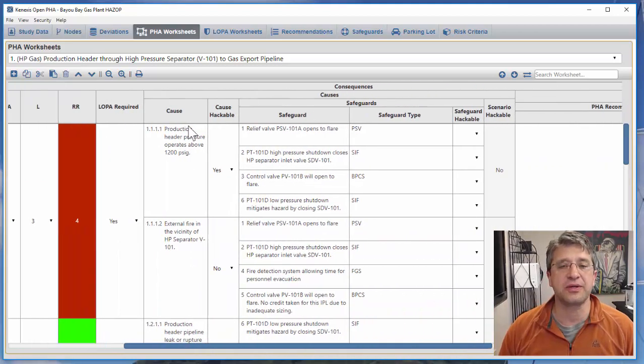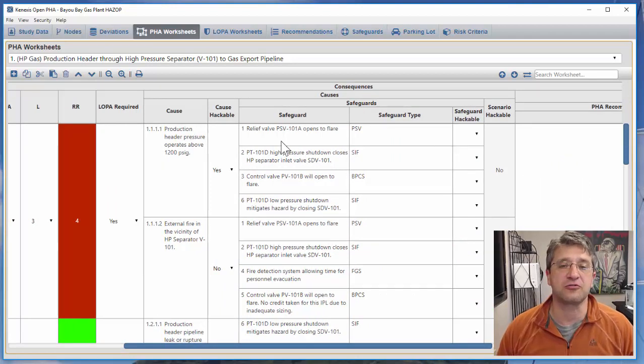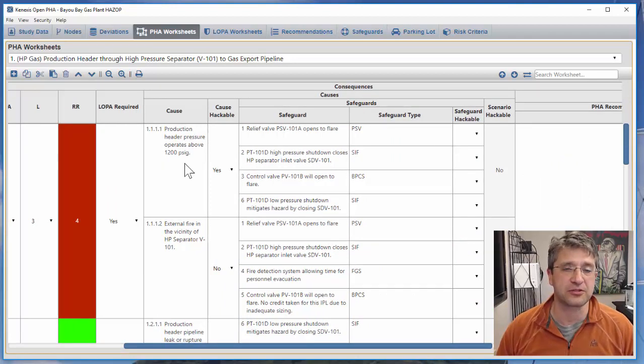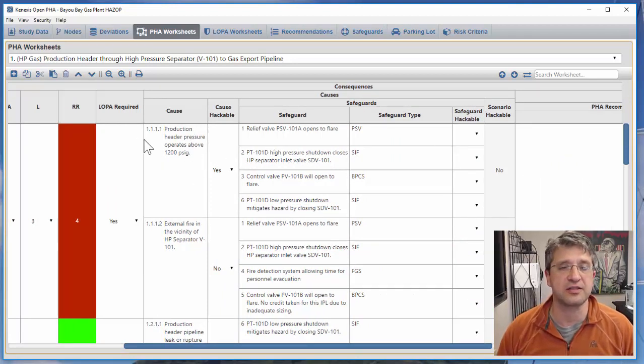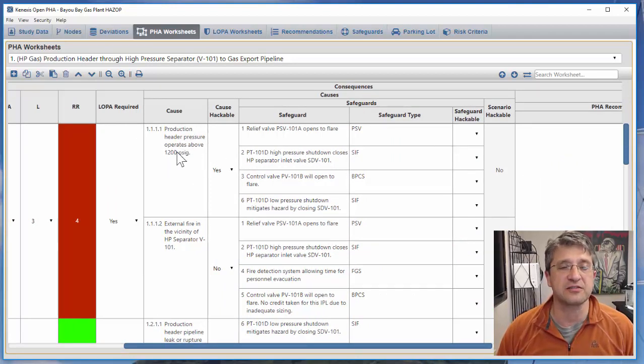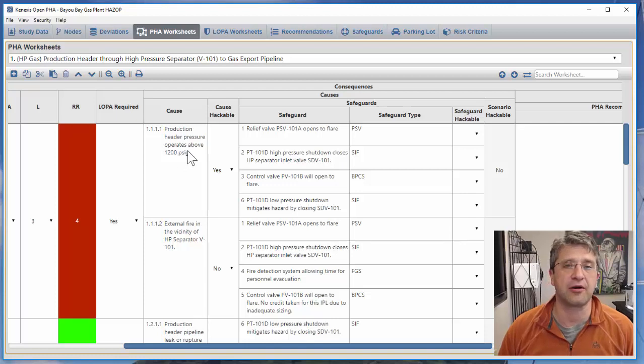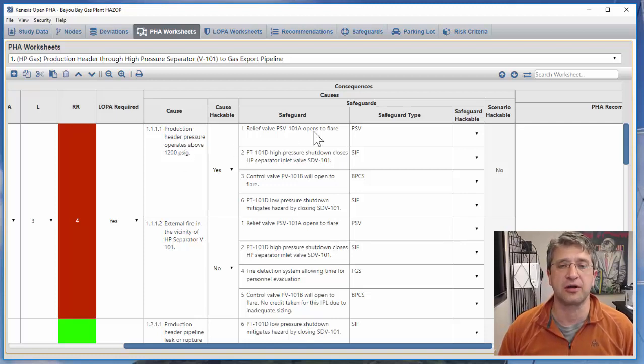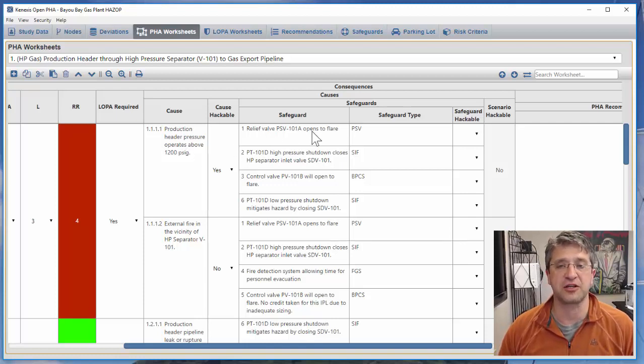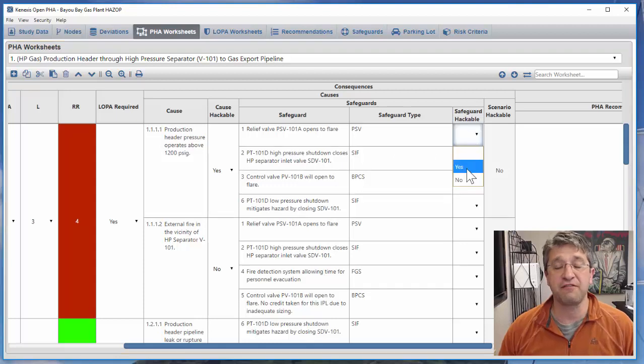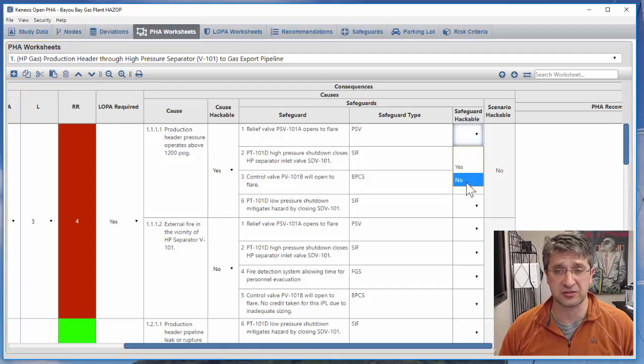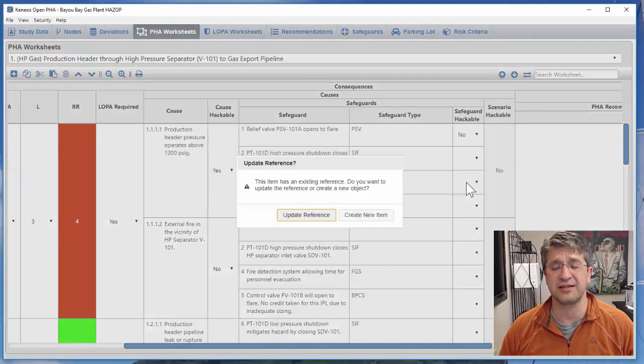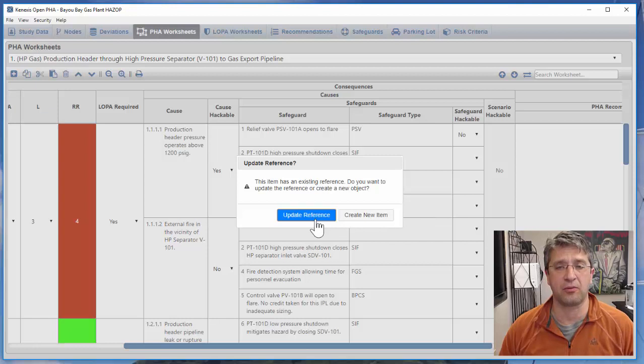Next we go over to all of the safeguards for that particular cause. In this case the safeguards against the production header operating over its design pressure include a relief valve that's going to open the flare header. A relief valve is a simple mechanical system so it is not hackable.